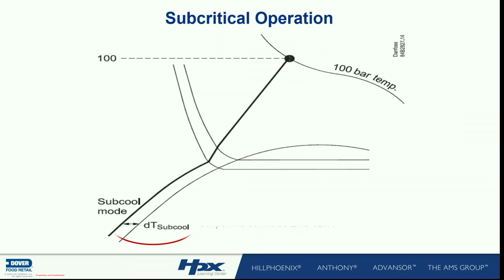First of all, intuitively, I'm running at 94 degrees, about 1,200 pounds. How far open is the high pressure control valve? Intuitively, what would you say? 75, wide ass open, yes or no? Yes. Any regulating valve that's wide open is now a ball valve, yes? This is not a ball valve.